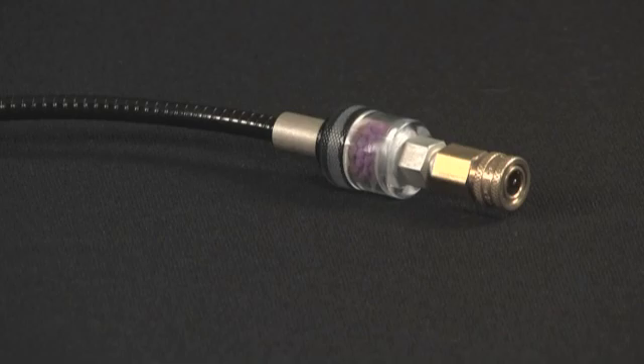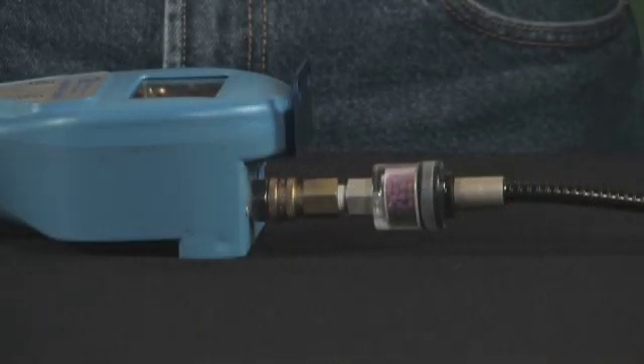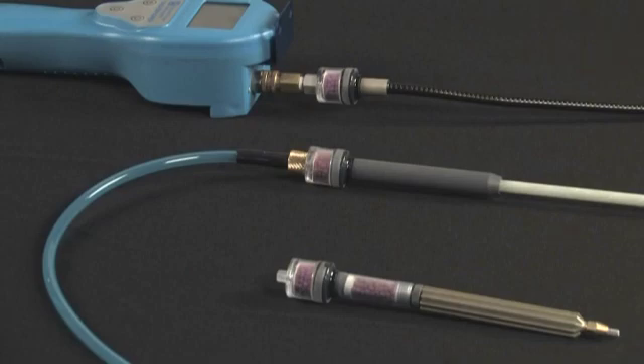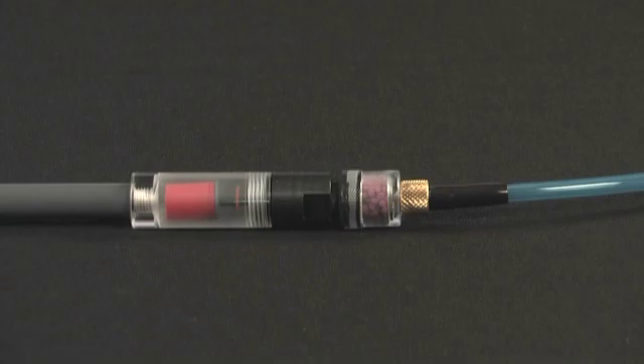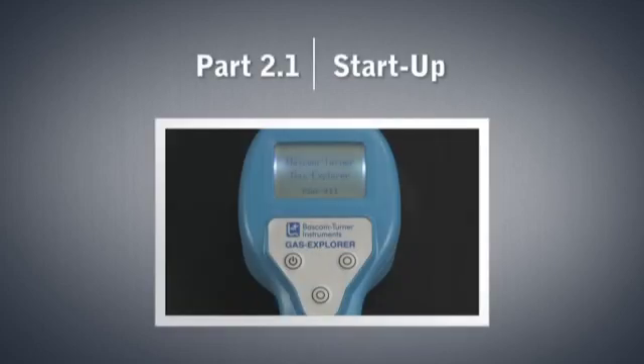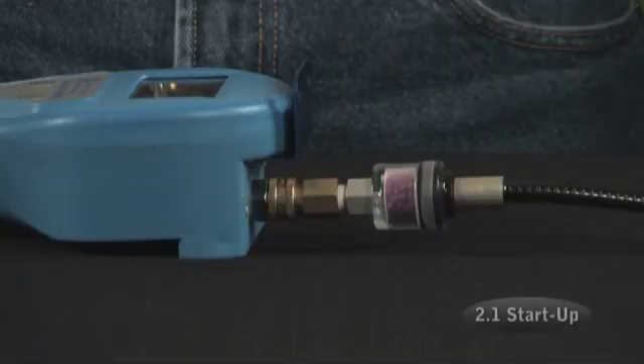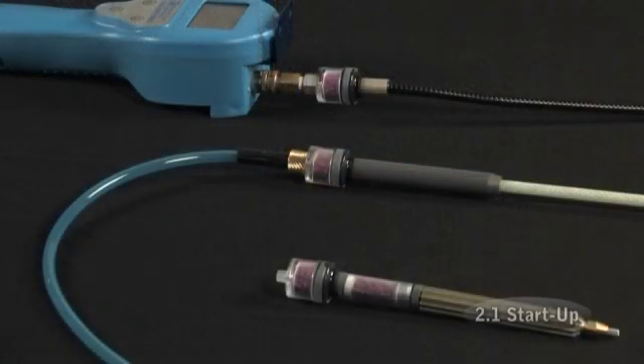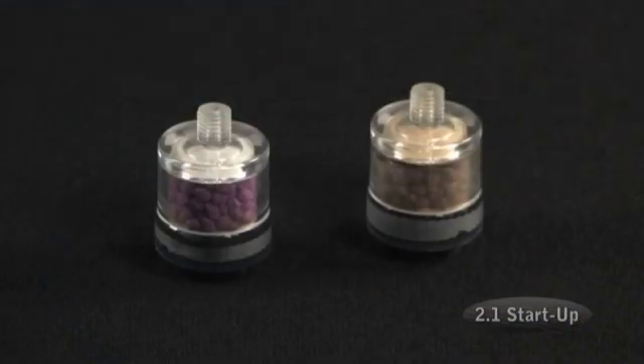The primary dust and water block filter must remain in place between the probe and the detector, no matter what probe is used, and even when an additional special filter is used. Before turning the detector on, be sure that the primary dust and water filter is in place between the detector and the probe you're using. When the media in the primary filter turns brown, usually in a month or 2, replace the filter.